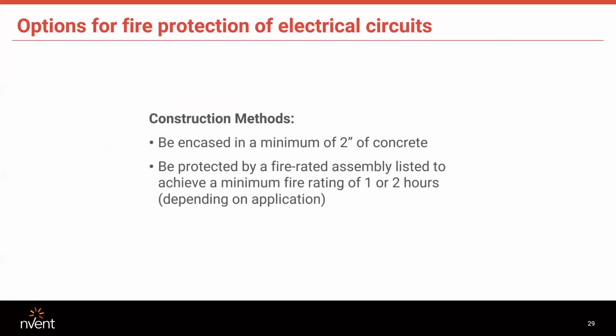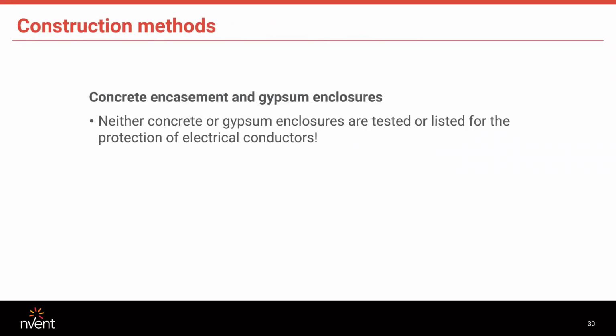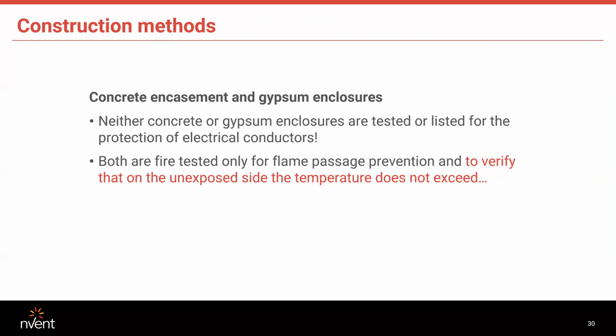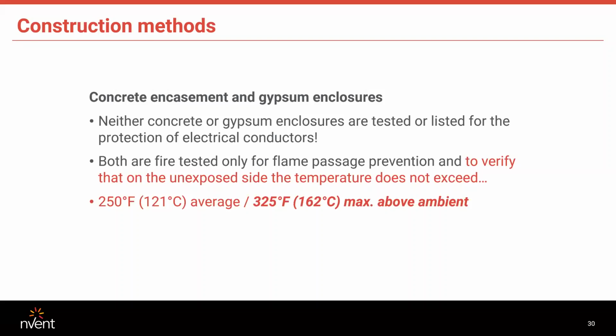Okay, now there are some methods, there are options. Construction methods, being encased in a minimum of 2 inches of concrete, is acceptable for the code. And also drywall enclosures are acceptable. But it's important to know, just as people in the construction and engineering community, that neither concrete nor gypsum enclosures are tested or listed for the protection of electrical conductors, even though they are approved. They're basically both fire tested only for flame passage prevention and to verify that on the unexposed side, the temperature does not exceed 325 degrees maximum above the ambient temperature.